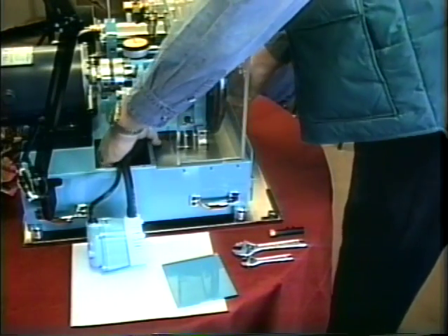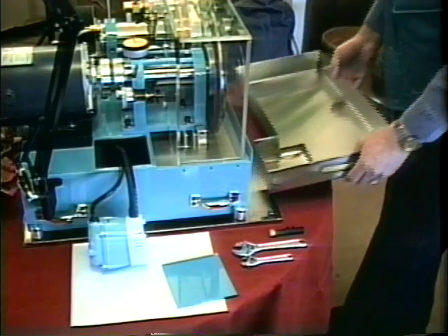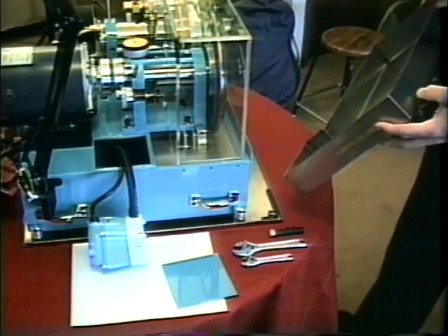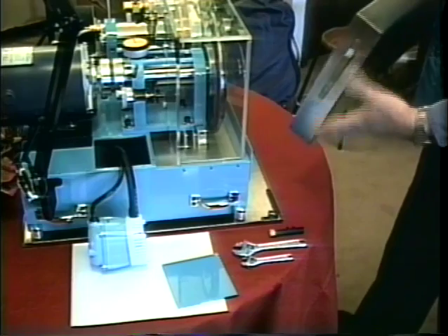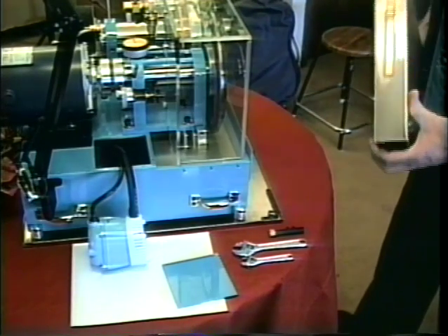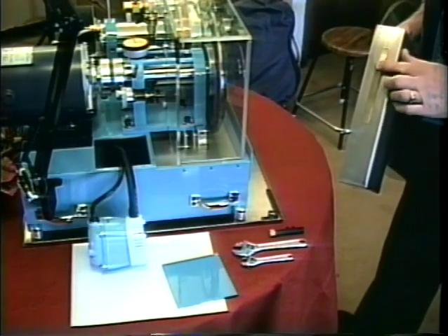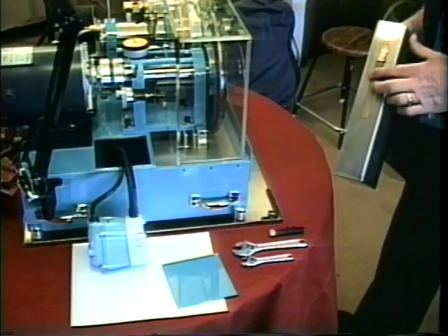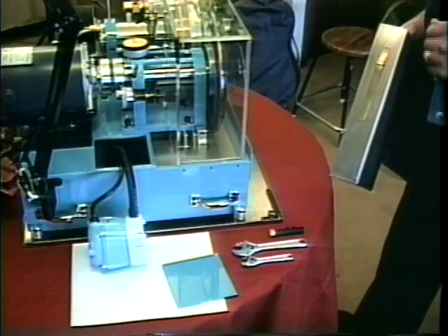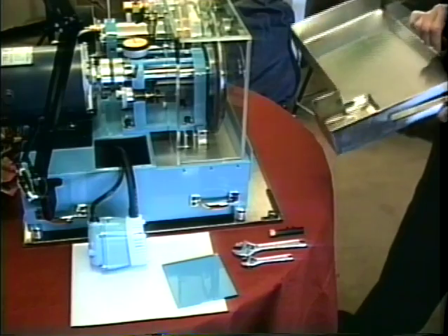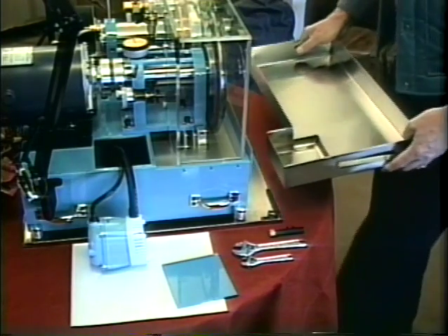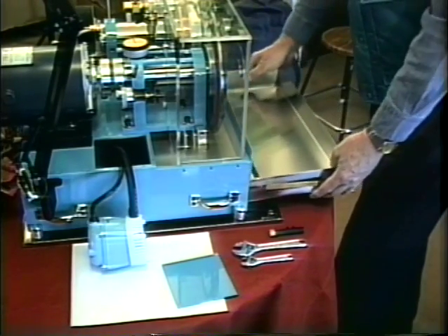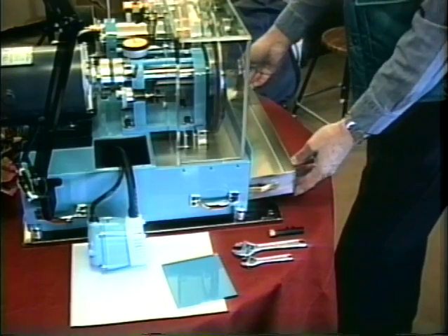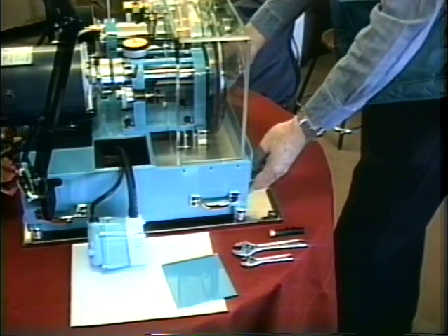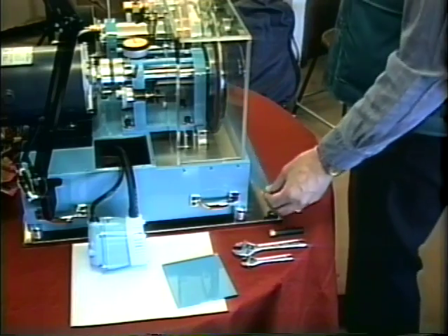Push the tray out from the back, and then you can pull it out from the front of the machine. This is really handy when you're changing coolant and doing general cleanup. There is a positioning spring on the left side of the tray. This spring urges the tray over to the right side of the machine frame where the drain tubes are. Push the tray straight in and then close the flap door.